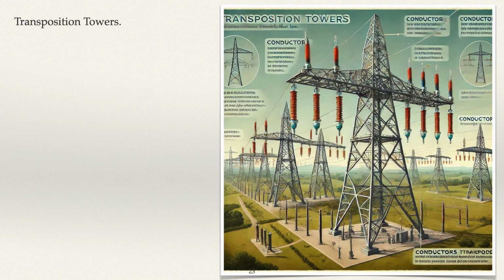Transposition towers are used to change the relative positions of conductors to balance electrical properties like inductance and capacitance. They contain additional insulators and hardware to facilitate conductor transposition, common in long transmission lines. Transposition towers are used for phase change within the circuit.